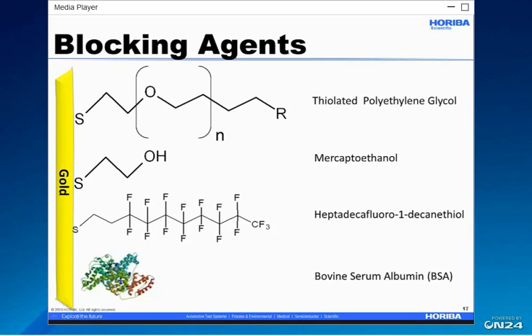A variety of chemical strategies have been reported for SPRI-based sensing. We found that the majority of the time, when working in serum or plasma, PEG works best as a blocking agent. Depending on your ligand, other blocking molecules may also be useful. A general rule is that all types of nonspecific binding to the surface must be kept as low as possible to prevent irrelevant signals interfering with the interpretation of specific interactions.